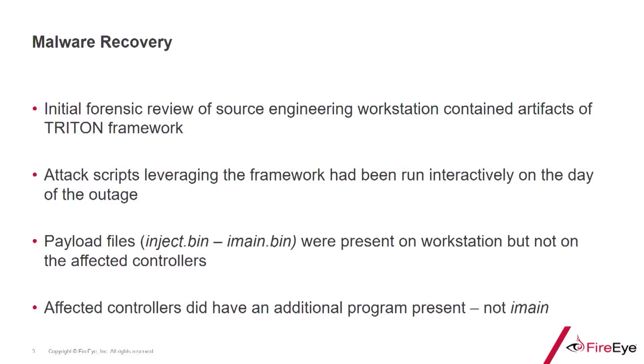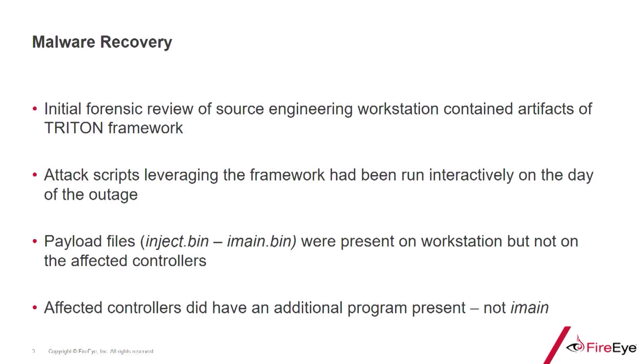This triggered a forensic review of that engineering workstation to help understand what occurred that day that led to application code being downloaded to the targeted controller. That led to the recovery of forensic artifacts from the engineering workstation containing both the attack script — Trilog.exe, the PyToExe compiled Python script — as well as the library.zip, which is the communications framework for arbitrary modification of Triconex state.